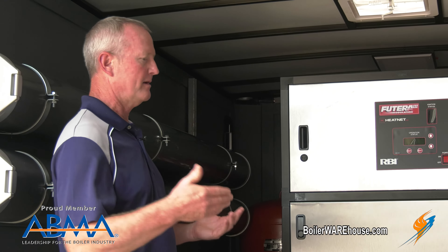We're at the back of the boiler where all this stuff happens. A typical system: you've got natural gas coming in, a regulator coming in, a vent coming off of it, a natural gas valve for control of the fuel going into the unit, make-up air coming in for the burner, exhaust coming out — that's the stack. These are the inlet and outlet piping for the flow of the water itself. A circulating pump provides continuous flow through the boiler. Pressure gauges show you what you have. A balancing valve lets you balance the flow. A relief valve protects the entire system.